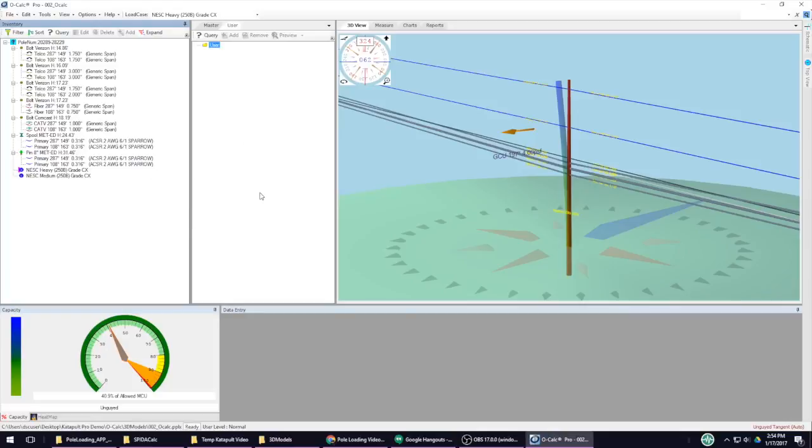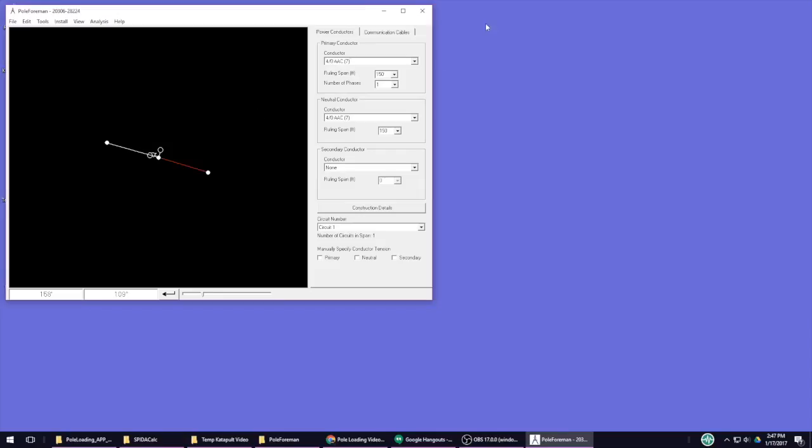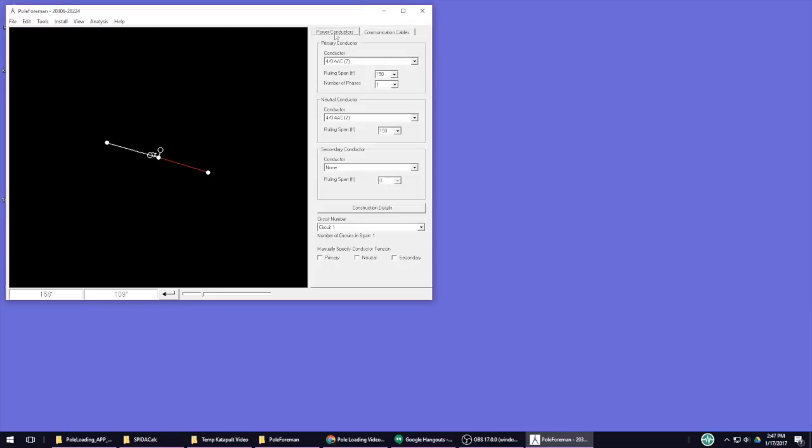Another downside would be Ocalc's pole loading results. Though the visual display is pretty, it doesn't show you as much details as the other programs. Next up is PoleForeman. PoleForeman is simple, consistent, and robust.